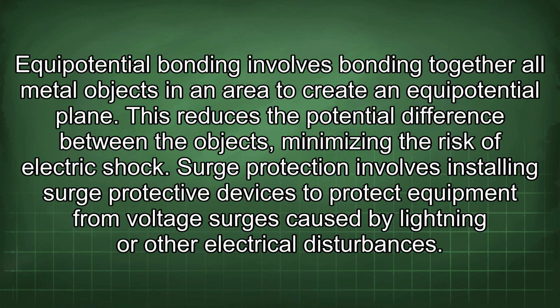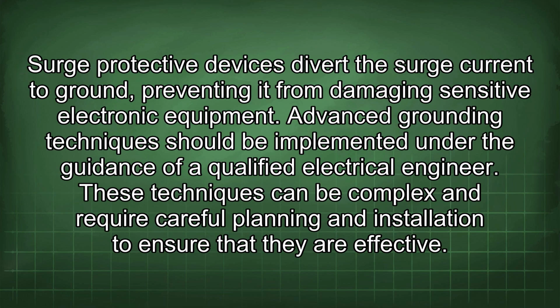electronic equipment. Equipotential bonding involves bonding together all metal objects in an area to create an equipotential plane. This reduces the potential difference between the objects, minimizing the risk of electric shock. Surge protection involves installing surge protective devices to protect equipment from voltage surges caused by lightning or other electrical disturbances. Surge protective devices divert the surge current to ground, preventing it from damaging sensitive electronic equipment. Advanced grounding techniques should be implemented under the guidance of a qualified electrical engineer. These techniques can be complex and require careful planning and installation to ensure that they are effective.